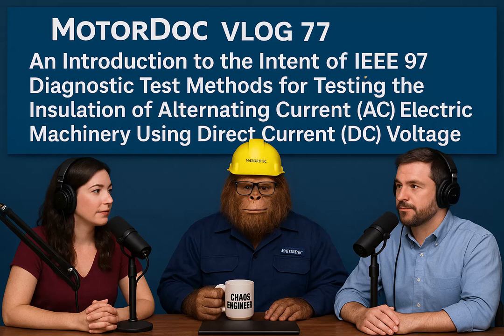Okay, like the main power cables connecting the machine to the switchgear. Yep. Long cables or older degraded cables, they can lower the overall IR values you measure. If you get readings that seem lower than expected, it's always good practice to disconnect the machine from the cables and retest just the winding itself. See if the cables were dragging the reading down. And for trending, you must be consistent. Either always test with cables connected or always test isolated.